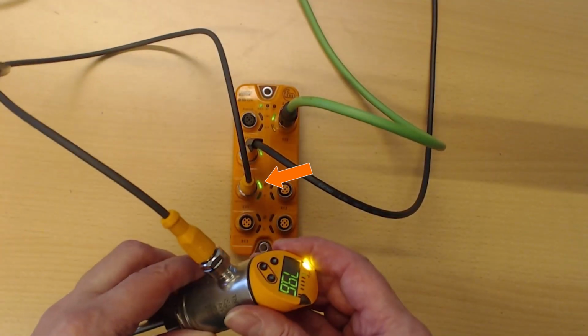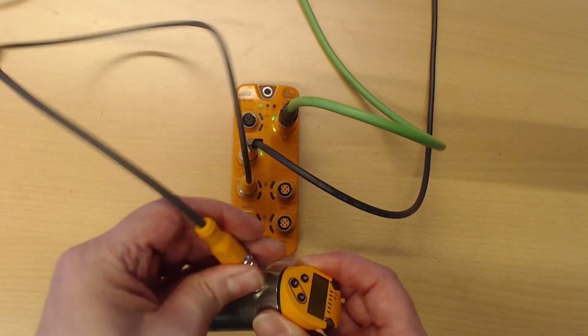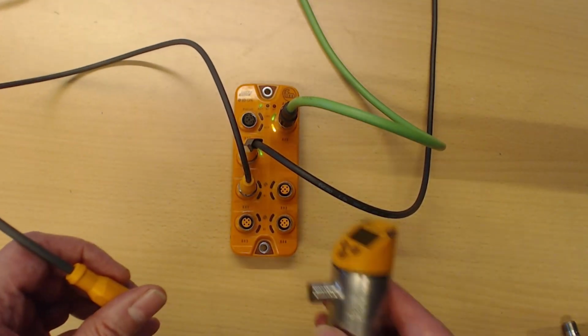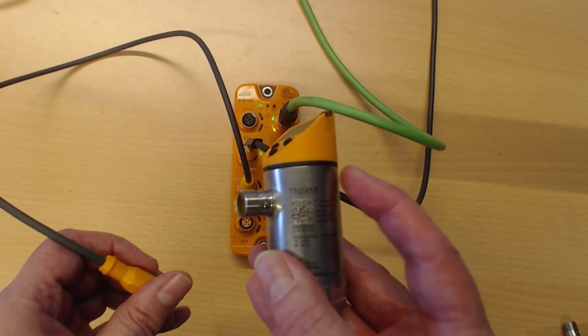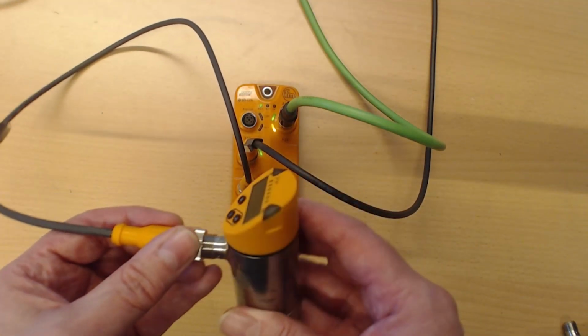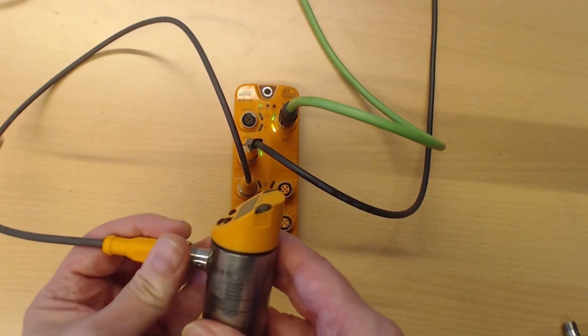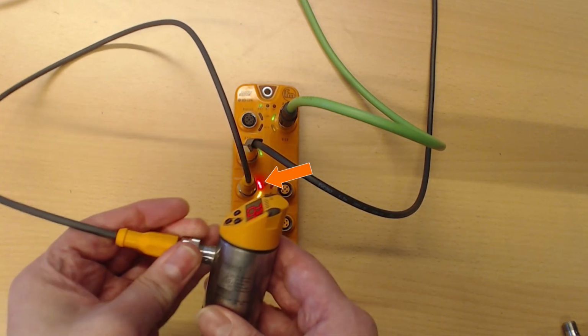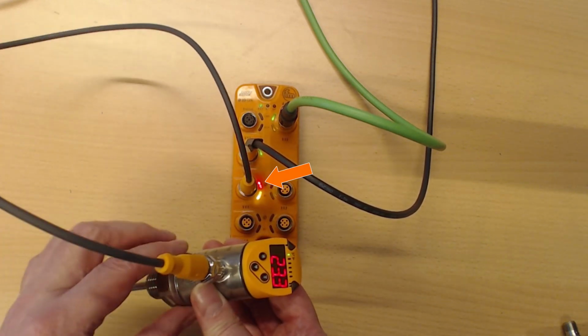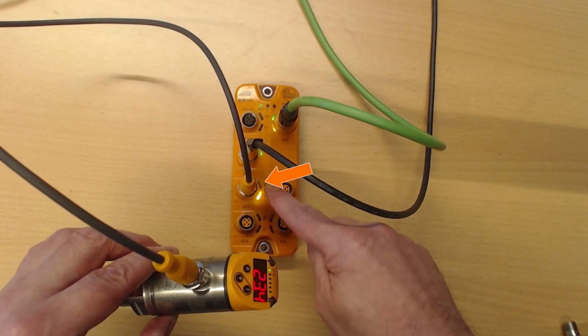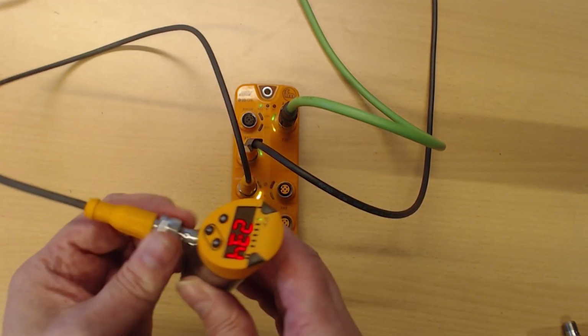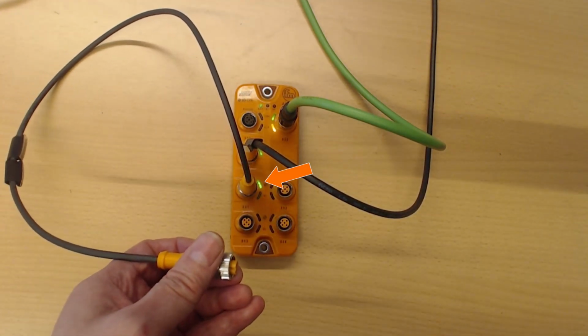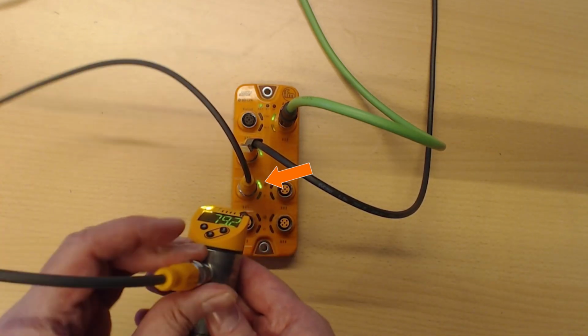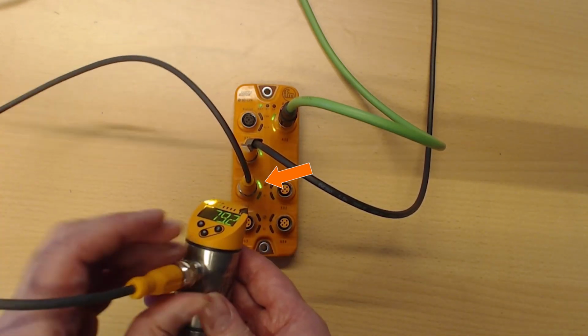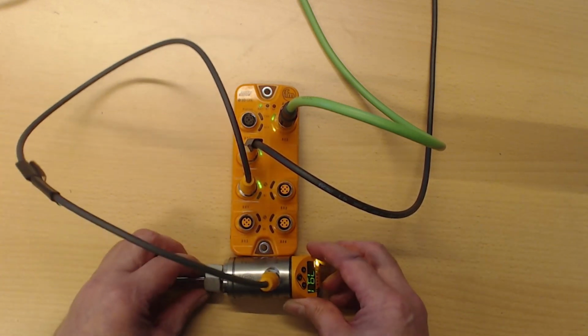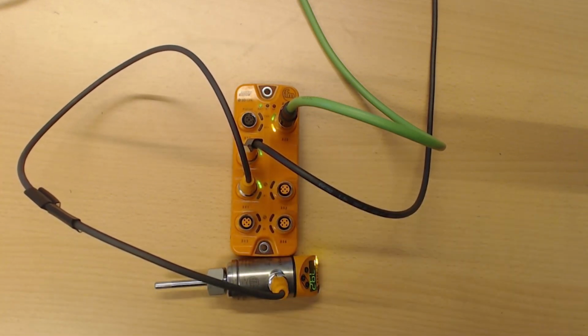Now we disconnect the M12 plug and connect a TN2415 instead of a TN7511. If an incorrect device with a different vendor or device ID is used, this will be detected by the master. The process values will not be read out, and the status LED will change to red. Only when the correct temperature sensor is reconnected will the LED color of port number 1 change back to green. The master accepts the wired sensor and reads out the process values again.